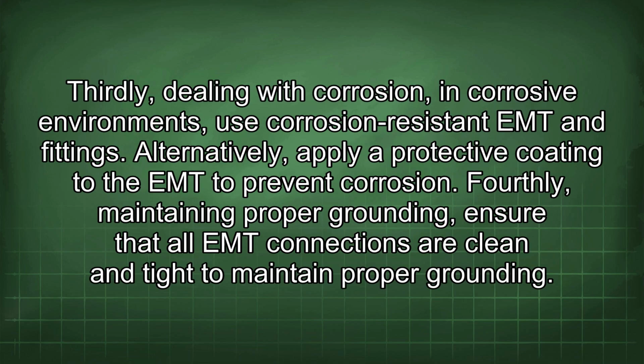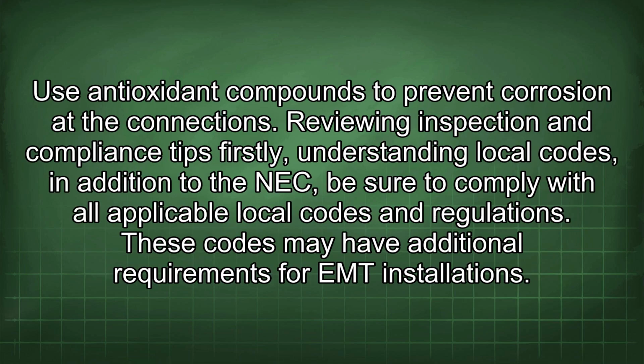Thirdly, dealing with corrosion. In corrosive environments, use corrosion-resistant EMT and fittings. Alternatively, apply protective coating to the EMT to prevent corrosion. Fourthly, maintaining proper grounding. Ensure that all EMT connections are clean and tight to maintain proper grounding. Use antioxidant compounds to prevent corrosion at the connections.